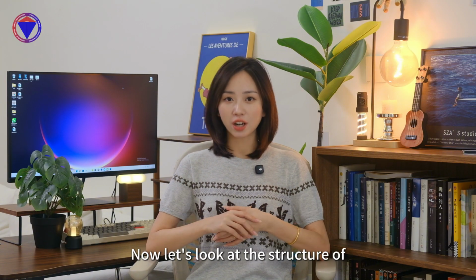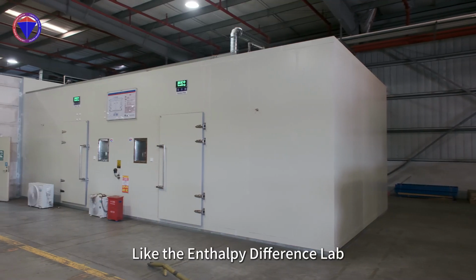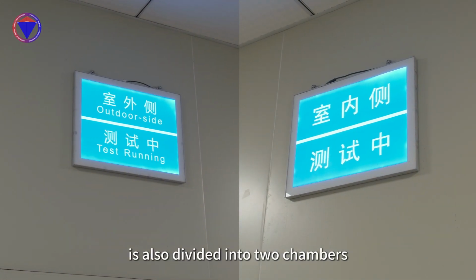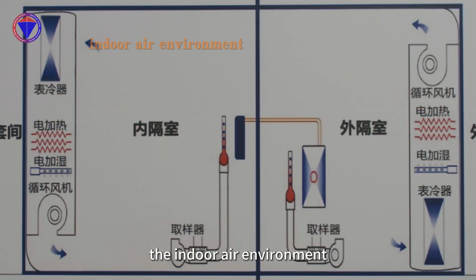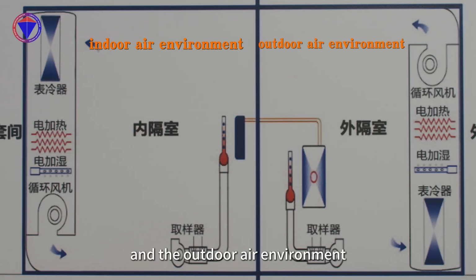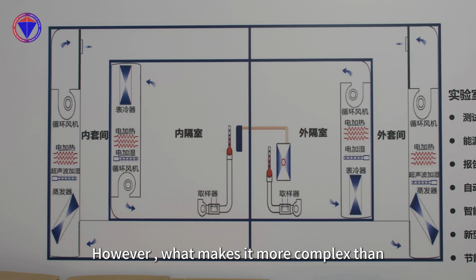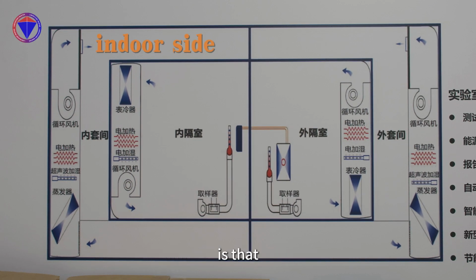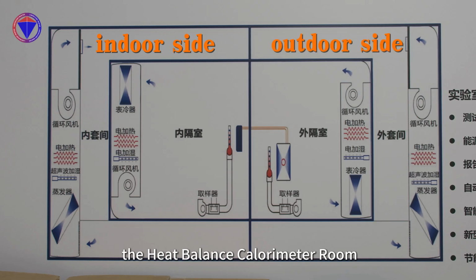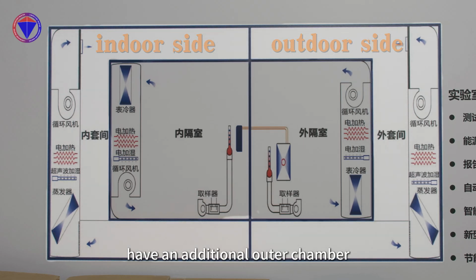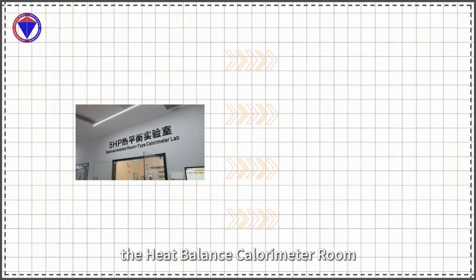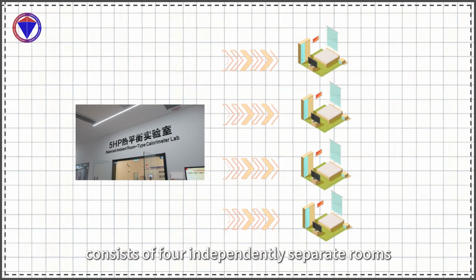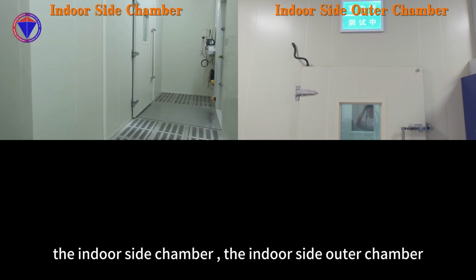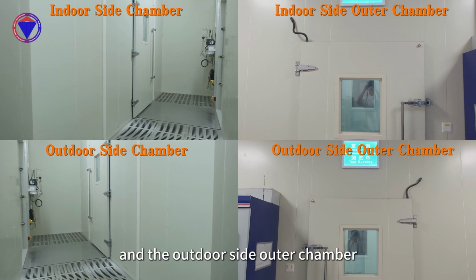Now, let's look at the structure of the Heat Balance Calorimeter Room. Like the enthalpy difference lab, the Heat Balance Calorimeter Room is also divided into two chambers, an indoor side and an outdoor side. These simulate the indoor air environment and the outdoor air environment, respectively, acting as the inner chamber of the room calorimeter. However, what makes it more complex than the enthalpy difference lab is that both the indoor and outdoor sides of the Heat Balance Calorimeter Room have an additional outer chamber. In other words, the Heat Balance Calorimeter Room consists of four independently separate rooms: the indoor side chamber, the indoor side outer chamber, the outdoor side chamber, and the outdoor side outer chamber.